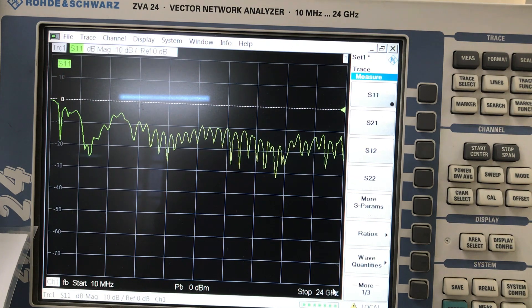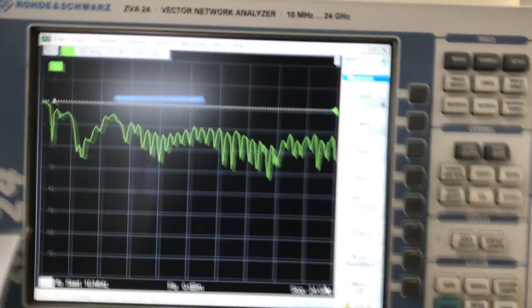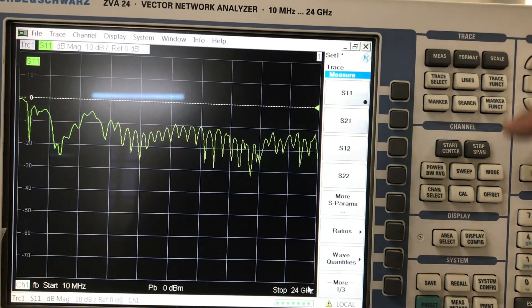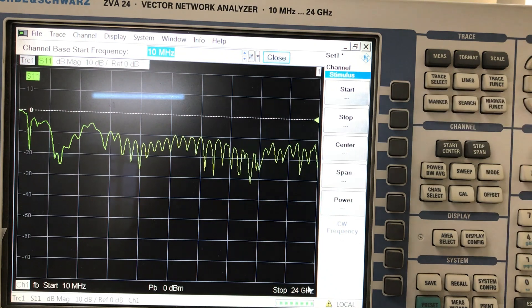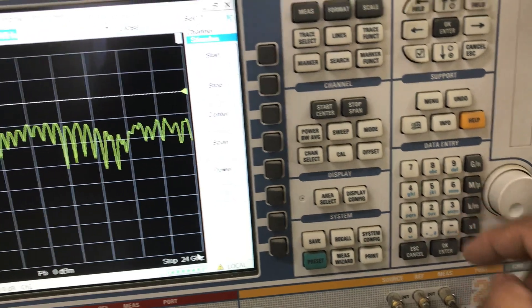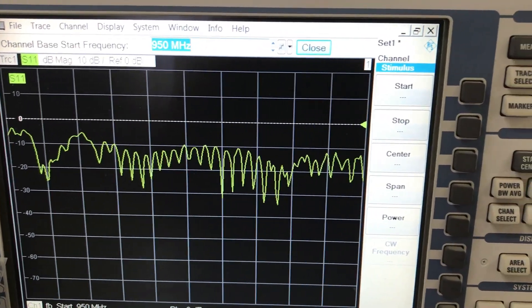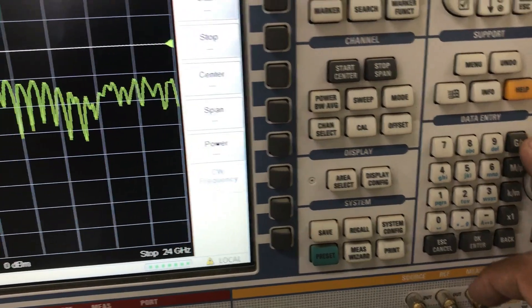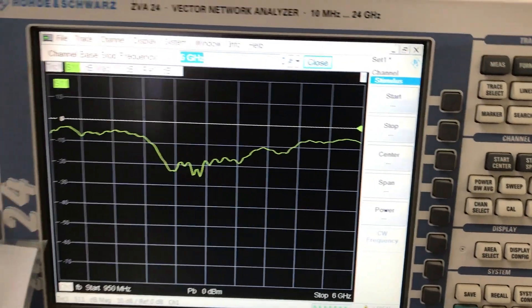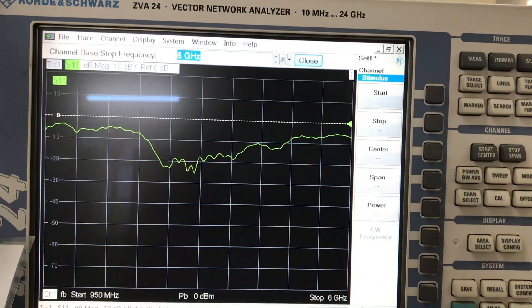The next thing I need to do is set the span. To set a span, go to the span settings and click on 'Start.' I'm going to type in my start frequency: 950 MHz. Then I'll set my stop frequency to 6 GHz. Now you can see the S11 of my antenna across that span.